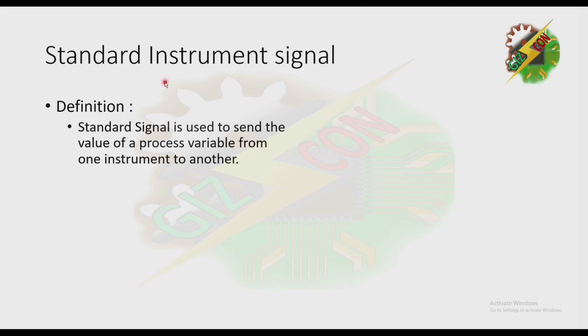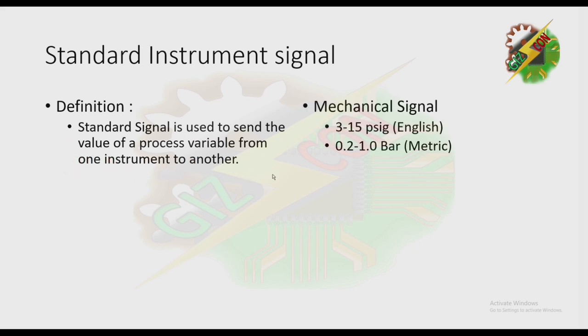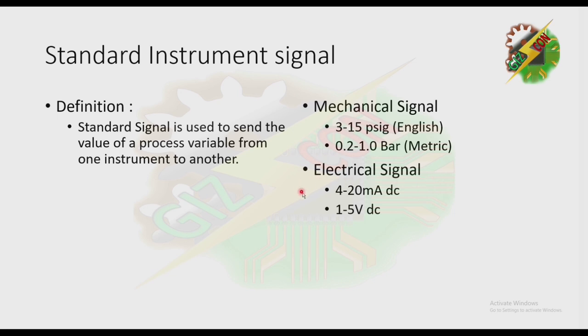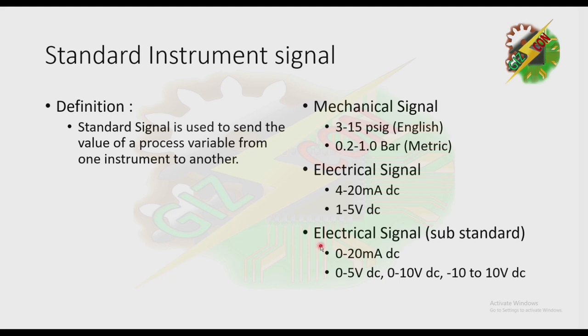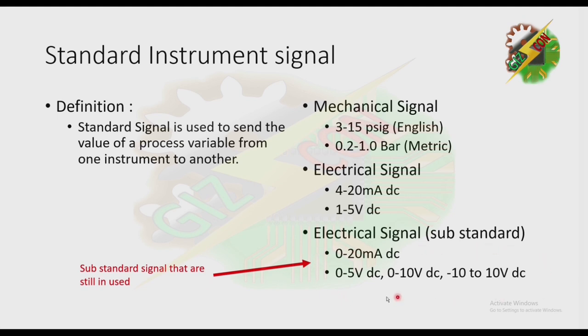Now let's discuss standard instrument signals. By definition, a standard signal is used to send the value of the process variable from one instrument to another. For standard mechanical signal, we have 3 to 15 PSIG for the English system, and 0.2 to 1.0 bar for the metric system. For standard electrical signal, we have 4 to 20 milliampere DC, and 1 to 5 volts DC. There are also substandard electrical signals still used on some instruments: 0 to 5 volts, 0 to 10 volts, and negative 10 to 10 volts.